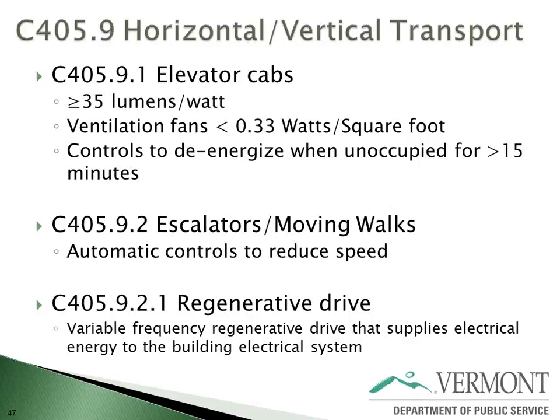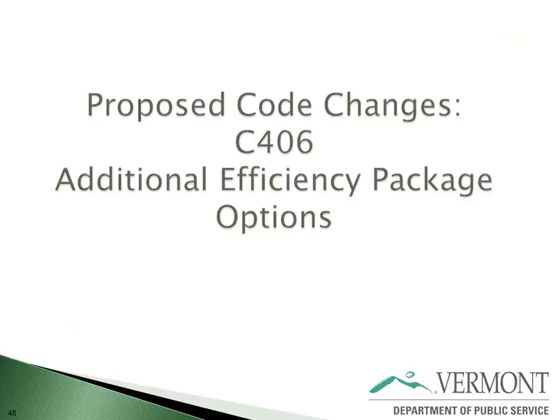There are also automatic controls to reduce speed on escalators and moving walks, and there are exceptions in there, but that gets at some energy use that might be wasted in those. And I heard at the last meeting that this requirement of regenerative drive is actually pretty standard and pretty easy to implement. It's a variable frequency drive that takes the load from the people coming down the escalator and uses that to supply energy back to the building. So you're generating your own electricity off the escalator, which I've never seen before myself.